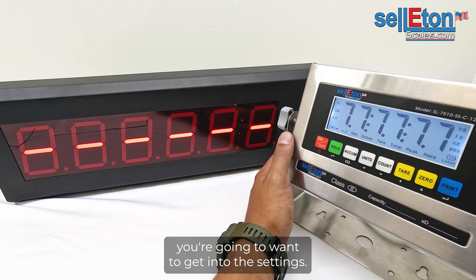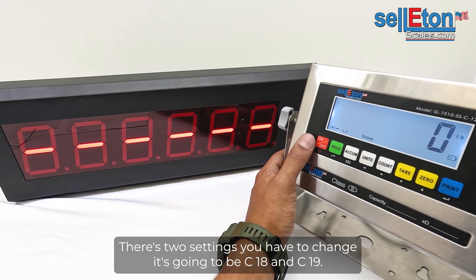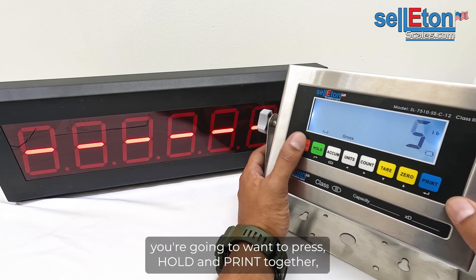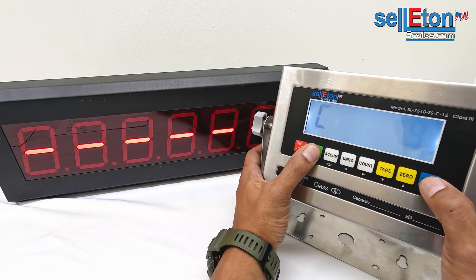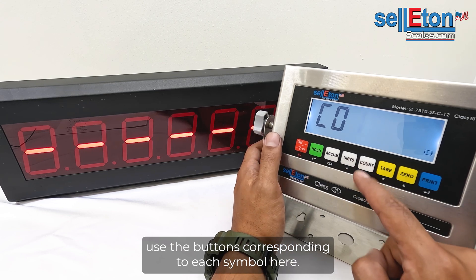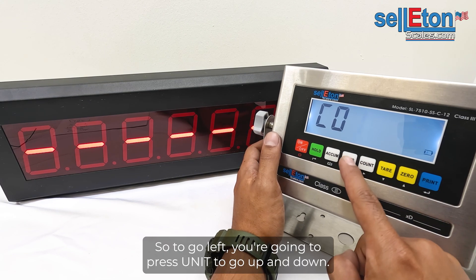Once your indicator is on, get into the settings — there are two settings we have to change: C18 and C19. To get into the settings, press HOLD and PRINT together. Then use the buttons corresponding to each symbol: to go left, press Unit; to go up and down, use Tare and Zero.